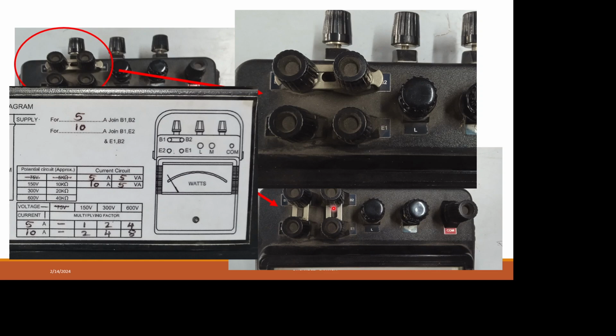Another thing you should note is that whenever you record the reading from this wattmeter, it must be multiplied by a multiplying factor. You can determine the multiplying factor depending upon what voltage and what current you are considering. In this chart, for 5 ampere at 150 volt the multiplying factor is 1, for 5 ampere at 300 volt it is 2, and for 5 ampere at 600 volt it is 4. Similarly, for 10 ampere at 150 volt it is 2, at 300 volt it is 4, and at 600 volt it is 8. So the multiplying factor can be determined from this particular chart.